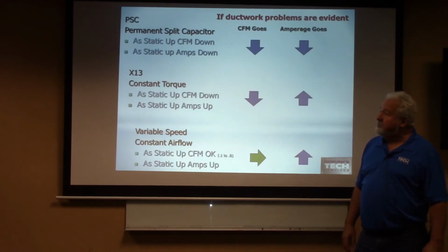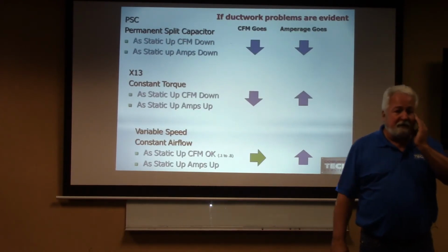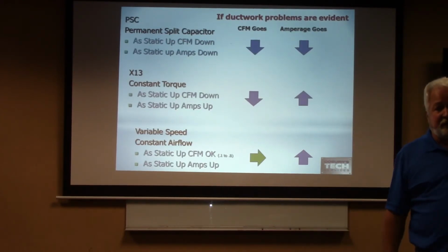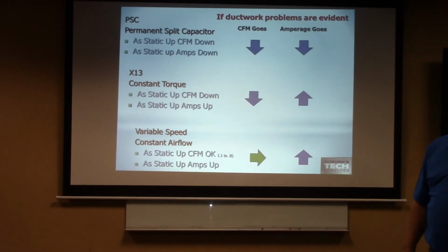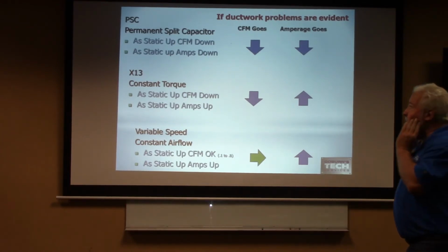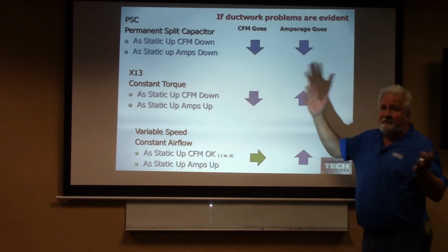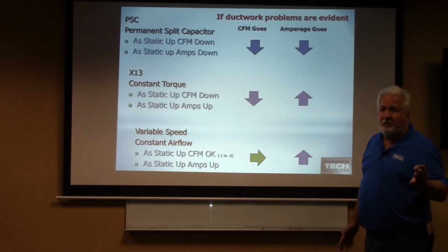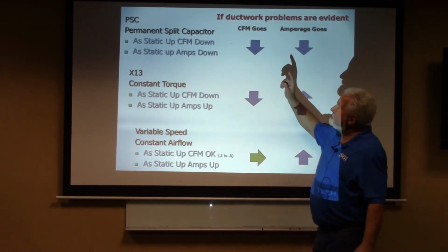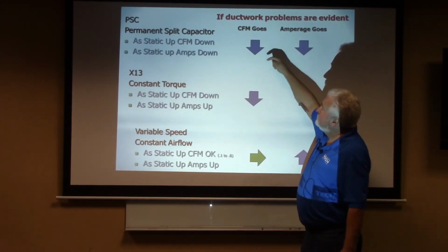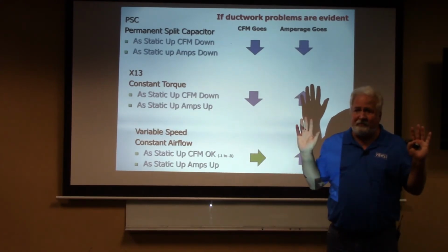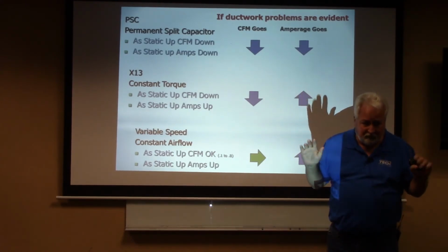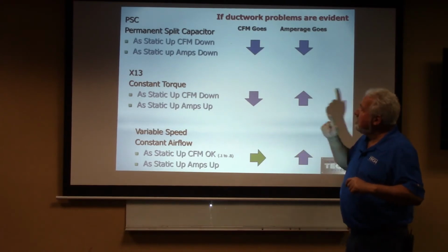Okay? All right. So here's a graph that Jody and I put together. I think this is really kind of cool. It's something I want you to pay attention to, because this is the thought process that's a little goofy. If I'm dealing with a PSC motor, as the static goes up, CFM goes down. So as the resistance inside that ductwork goes up, what happens to the CFM? It drops off. All right.